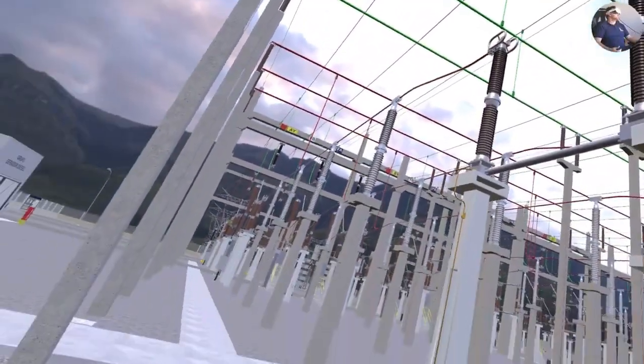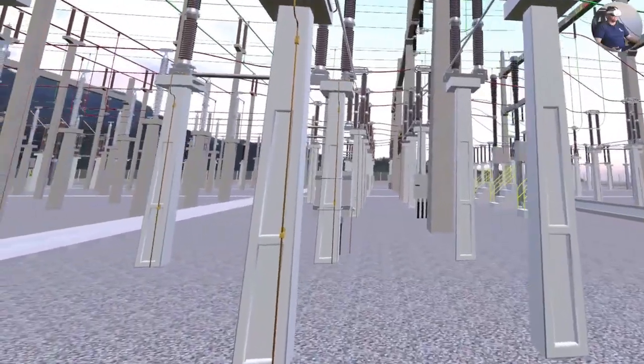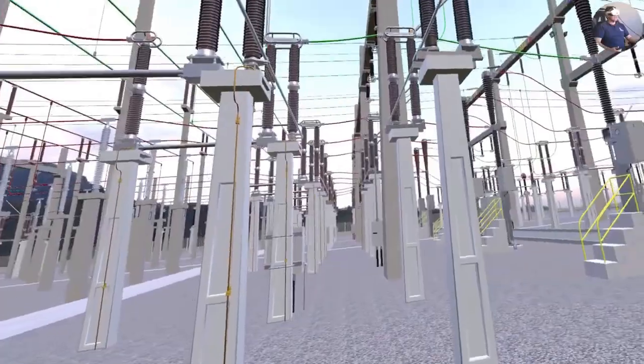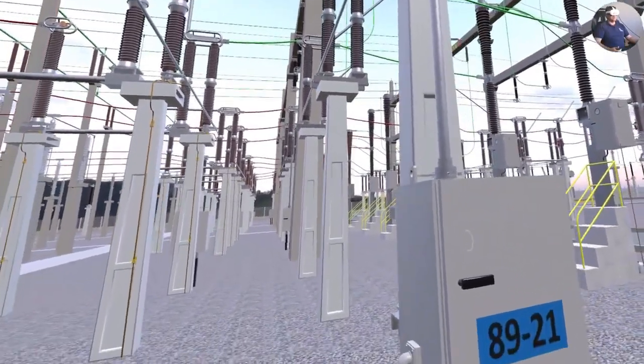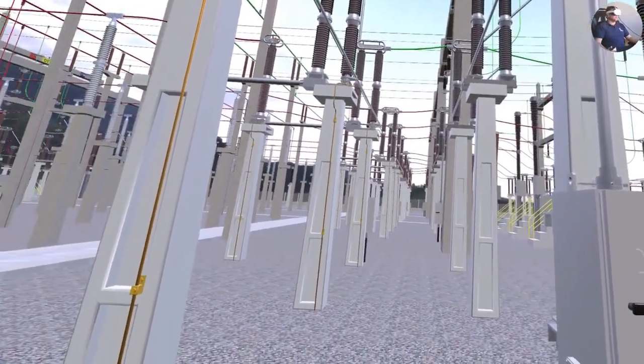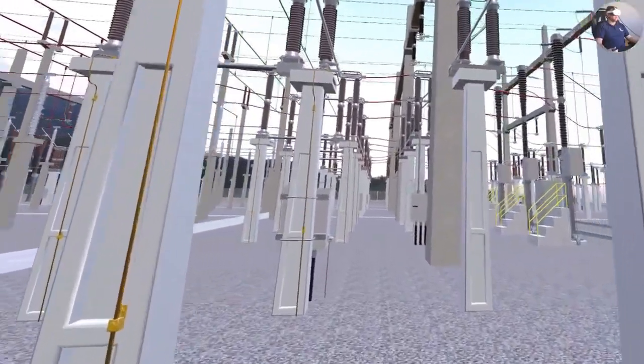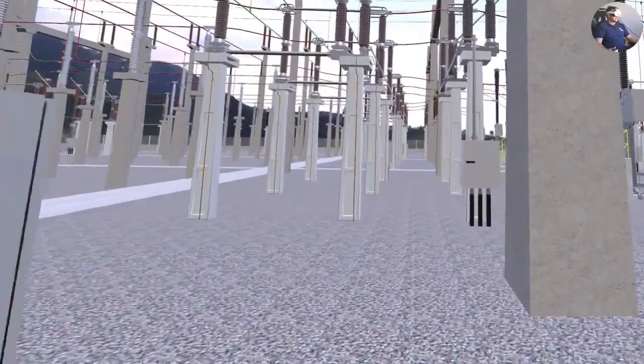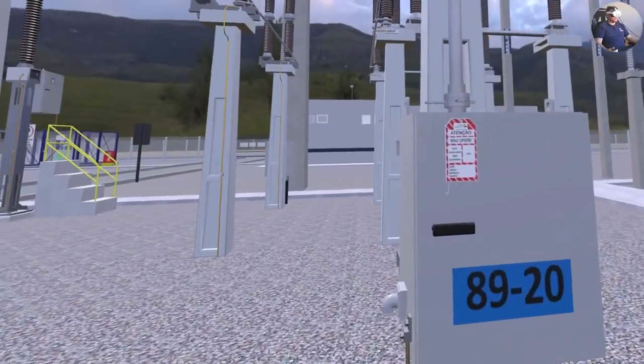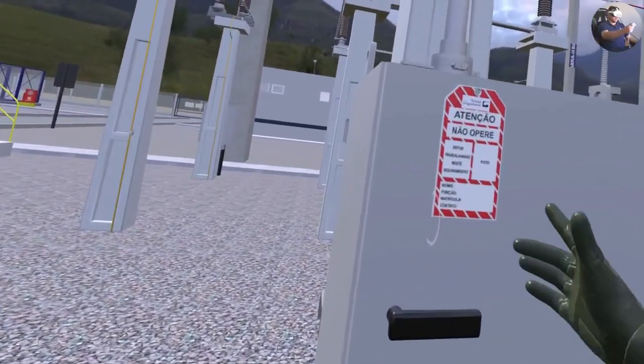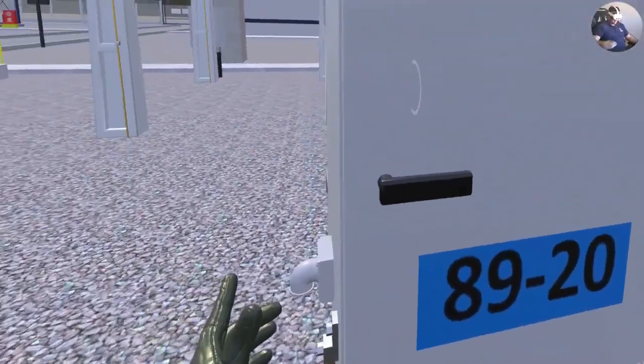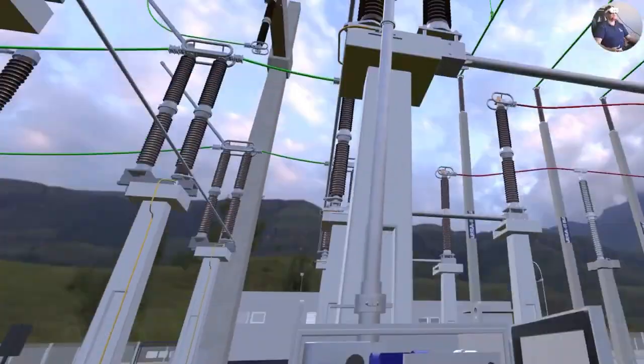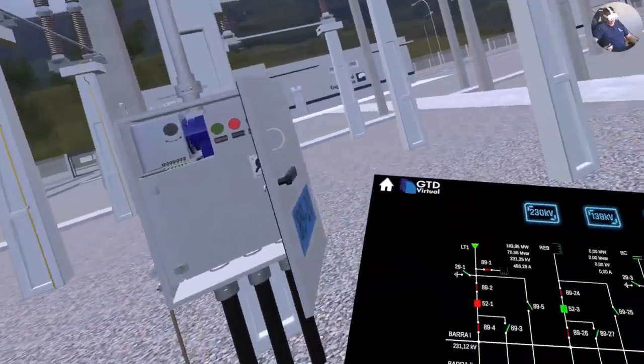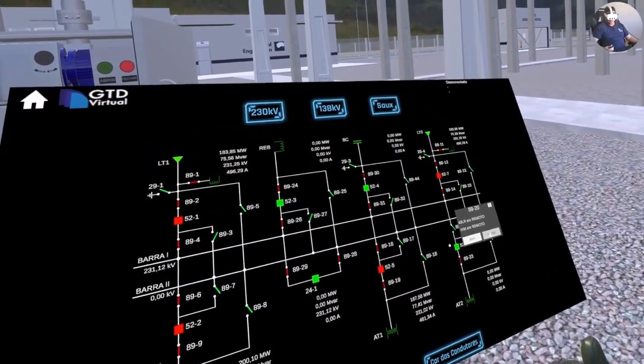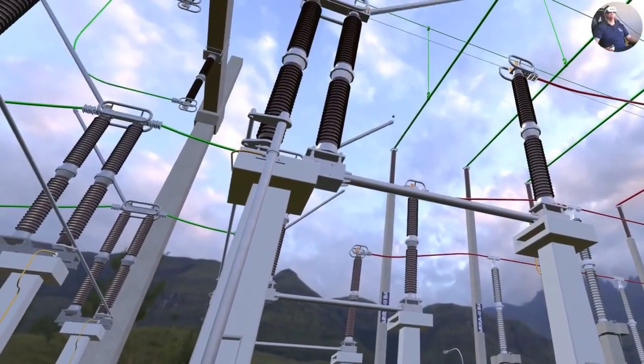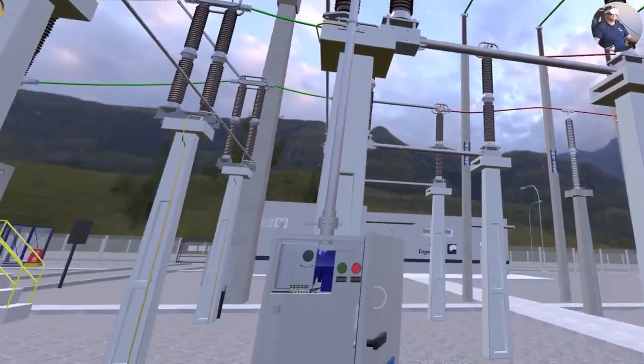We're going to close the disconnect switch for bus 1, which is this one. I could, everyone, return this function, depending on the substation's operating setup, it could operate here on bus 2, right? But then I'd have to perform another maneuver here, which is also closing perhaps the bus tie circuit breaker, right? So these configurations, everyone, will depend a lot on the substation, okay? It really depends on how we are going to operate that substation. So let's remove the safety tag here as well. Let's go ahead and switch to remote here. And then give the closing command, which is 8920, right? 8920 for bus 1. Close. Closed successfully.